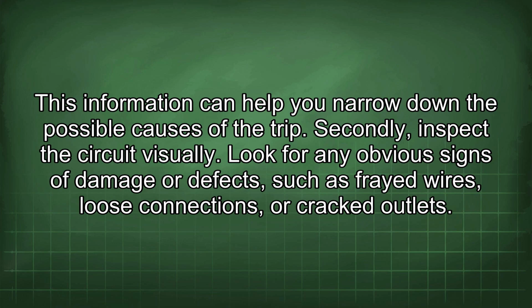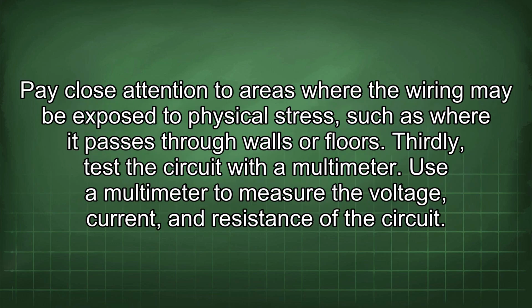Secondly, inspect the circuit visually. Look for any obvious signs of damage or defects, such as frayed wires, loose connections, or cracked outlets. Pay close attention to areas where the wiring may be exposed to physical stress, such as where it passes through walls or floors. Thirdly, test the circuit with a multimeter.